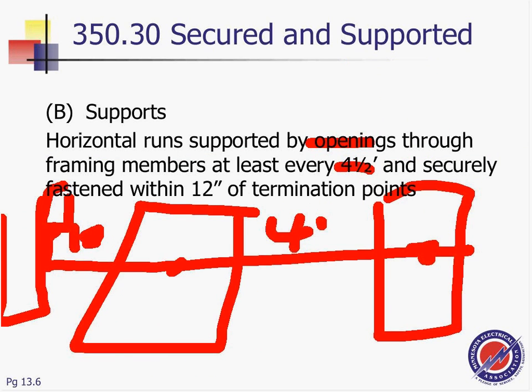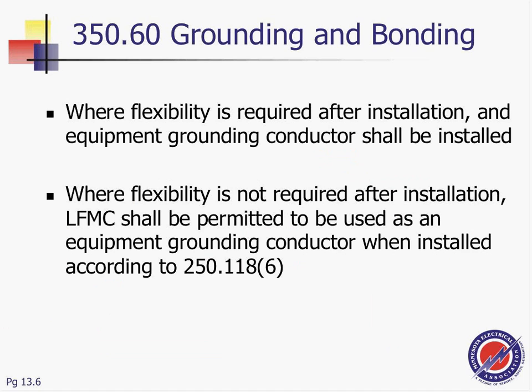We talked about the support. Flexibility, guys, if you need flexibility, which is why we use them, then you need to pull an equipment grounding conductor, no question asked. There are rules for using it as an equipment grounding conductor where there is no flexibility. So, friend, if you are tying it to a machine, you have to pull your equipment grounding conductor. The time you don't need to pull an equipment grounding conductor is if you are using it to tie to a fixture. Other than that, everything needs flexibility, vibration, and so forth, and fixtures.